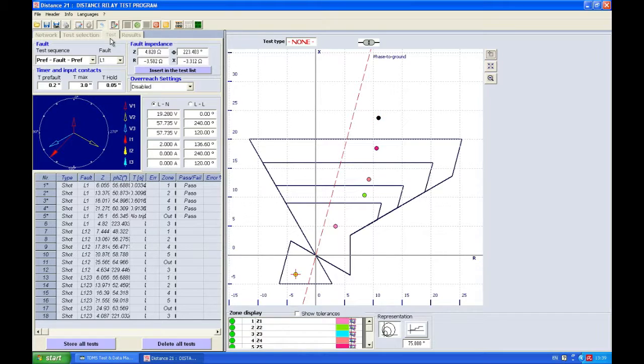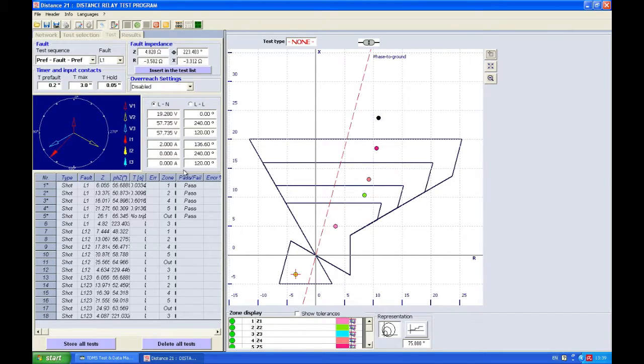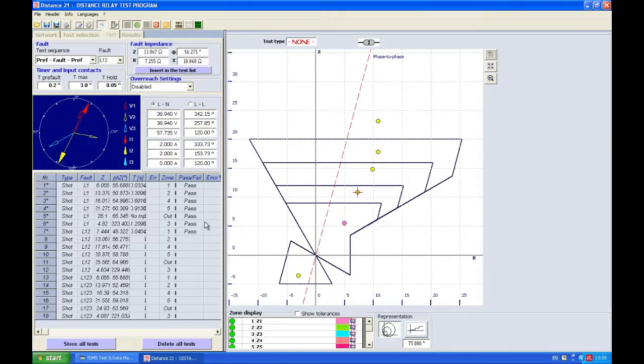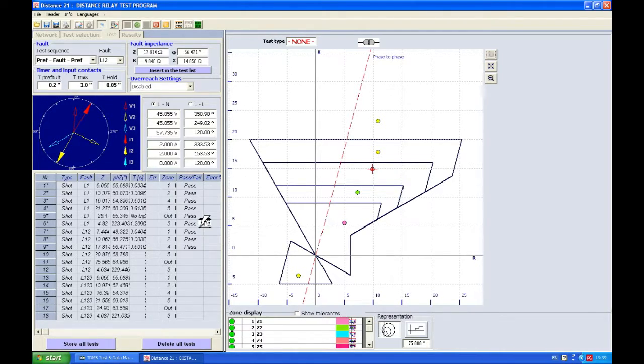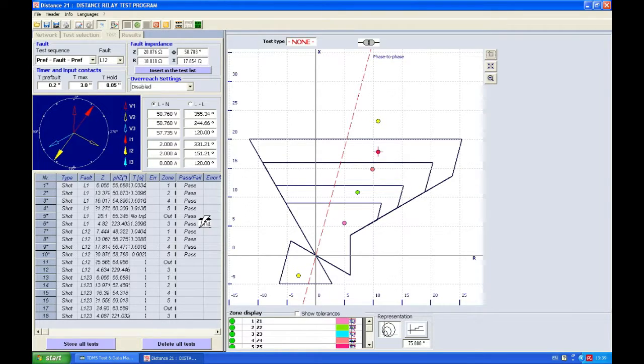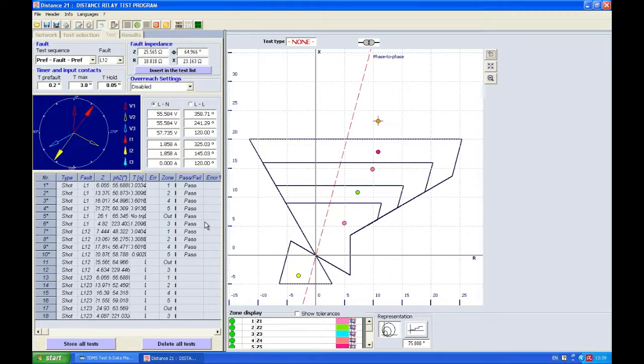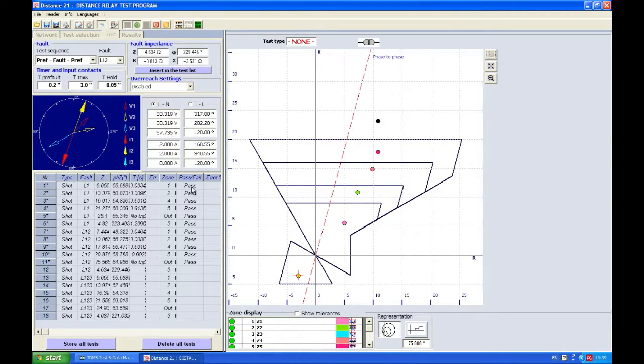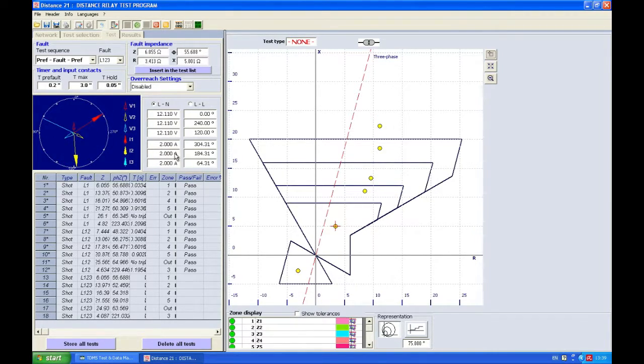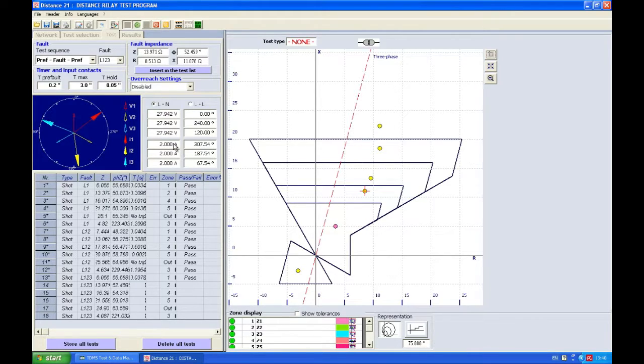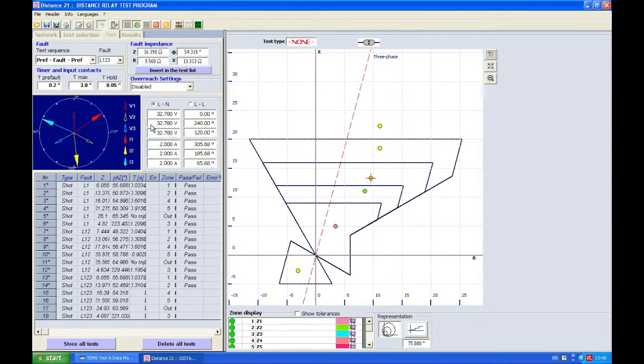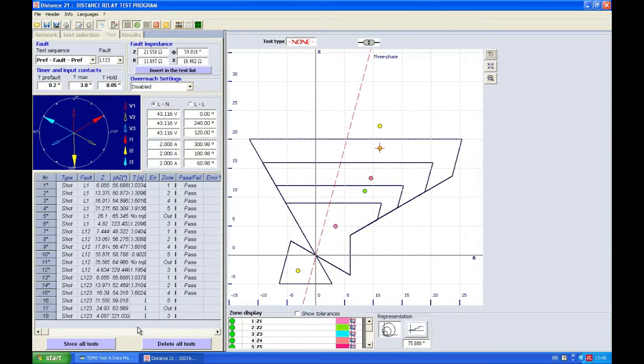Right now we have fully tested phase one. Now we're testing phase-to-phase. We see that we have pass on all these elements, and of course if we observe what's going on here, we see that two currents were changing. Now all three currents would be changing—all three voltages to be more exact, because it's a three-phase fault.